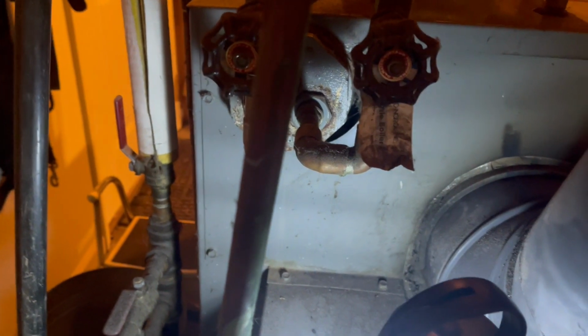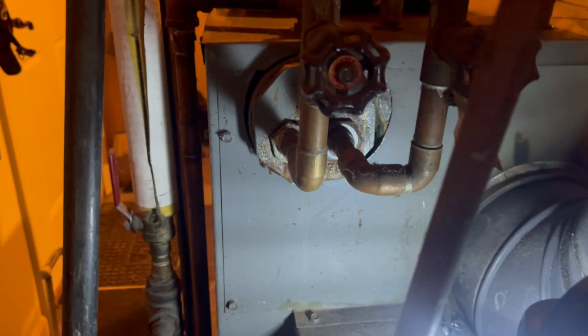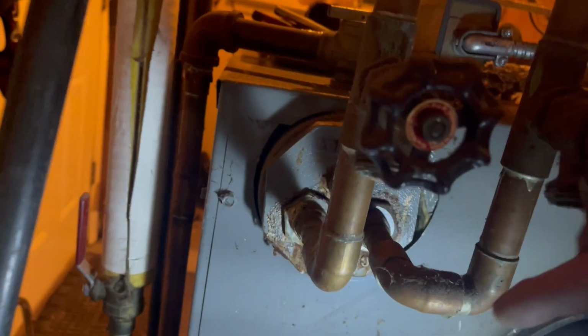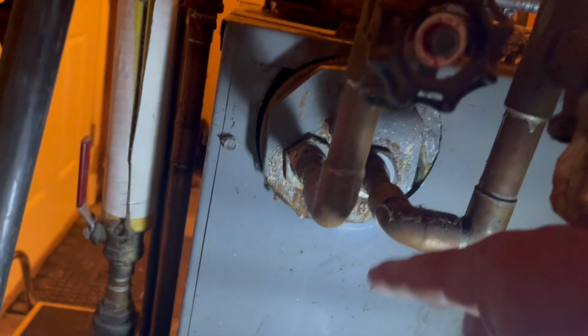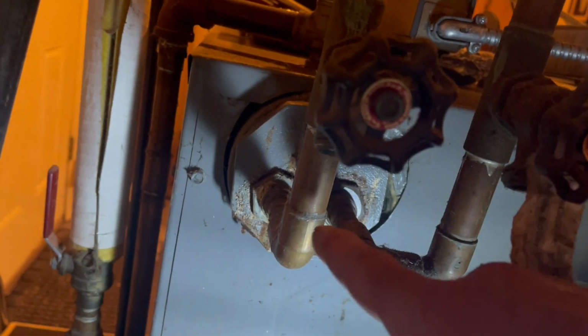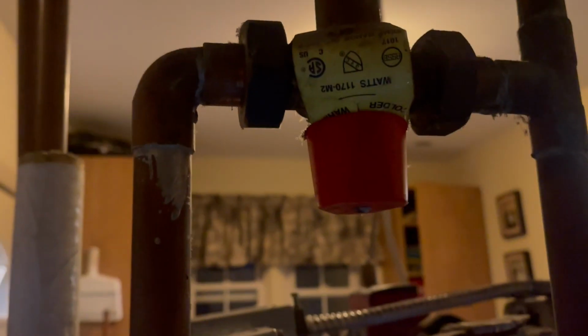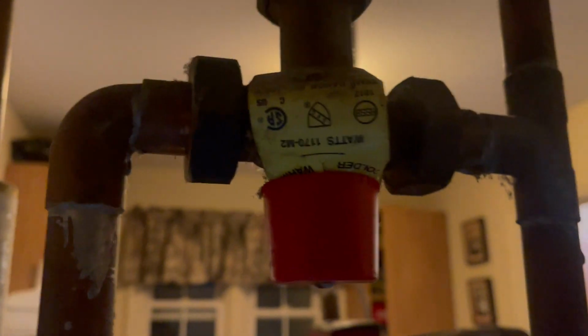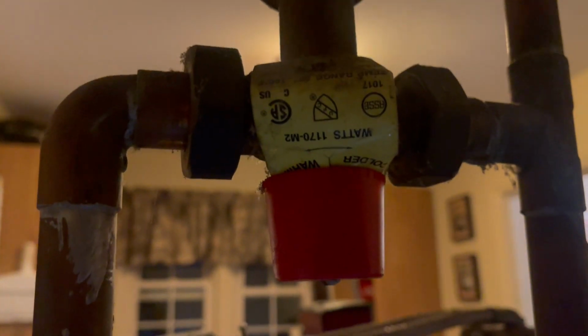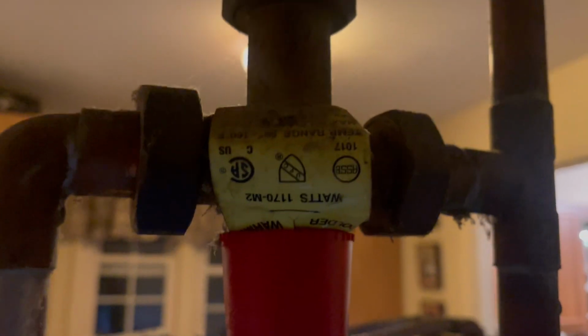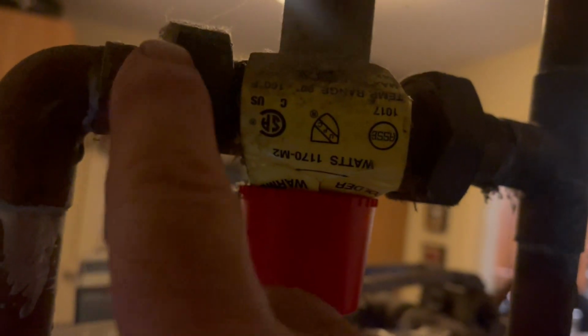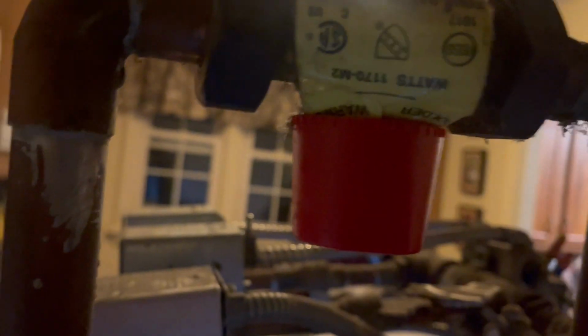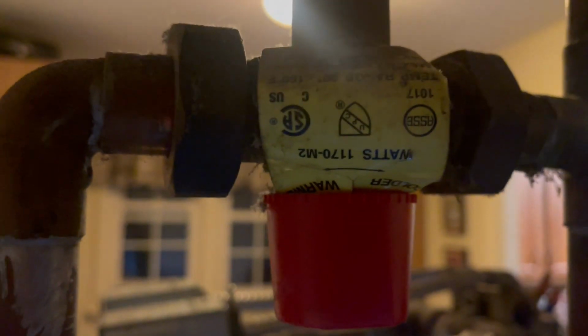Let's talk free hot water. All right, we're in the back of my boiler, and what you're looking at is a domestic hot water coil. Cold water comes in here, goes through a tube submerged in the hot water of the boiler, comes out here screaming hot. Now, because it is screaming hot, because the boiler runs at 180, and you don't want 180 degree water coming out of your tap, it has to go through this thing, a mixing valve. Cold water over here, and it will be mixed with the hot water to provide 120 degree water or so, based on how you adjust this valve. Voila, hot water for this side of the house.